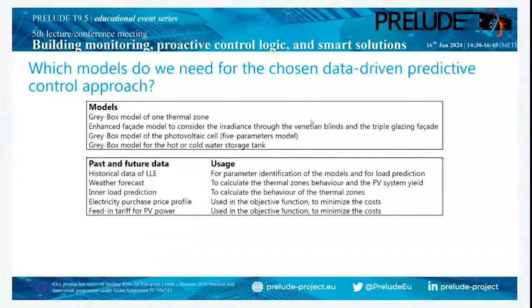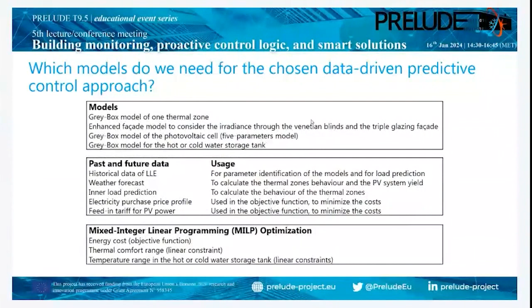With all this information, we use mixed integer linear programming optimization, with the objective function being to minimize the energy costs for the next 24 hours, which is our forecast horizon. We also have constraints: the thermal comfort range, as shown in the principal scheme, and the temperature range in the hot or cold water storage tank.